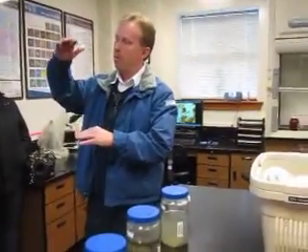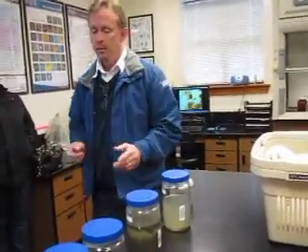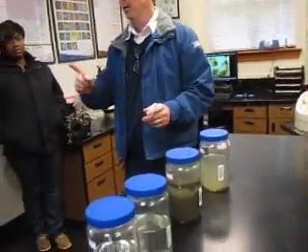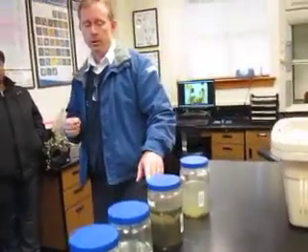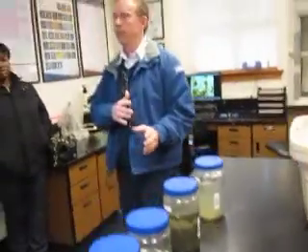Depending on how much you let it get out of check, depends on how much you can bring it back, how long it would take to get it back into check. The problem is when you waste off too much, that is a big problem because these microbes only grow so fast. So if you waste most of your bugs out of your system, it can take a substantial amount of time to get you back on track.